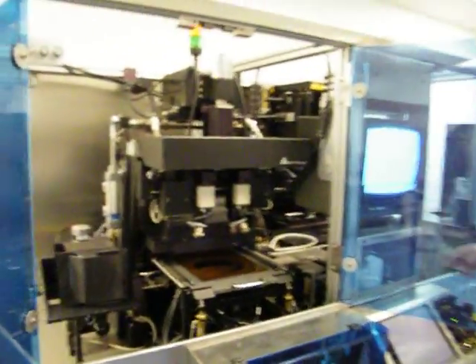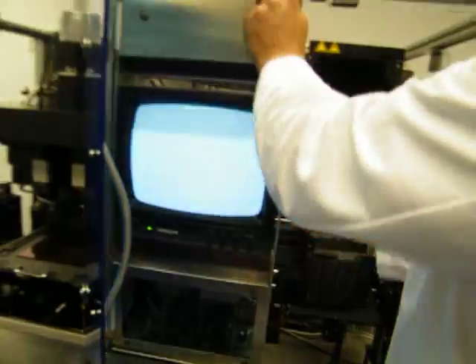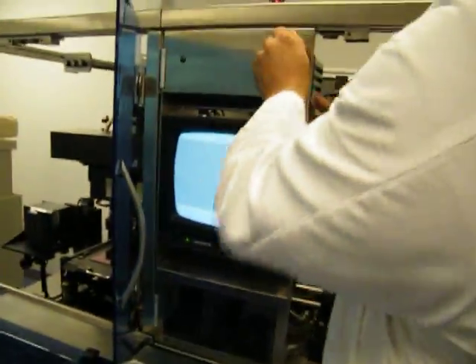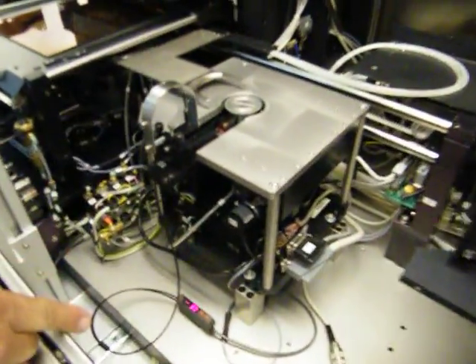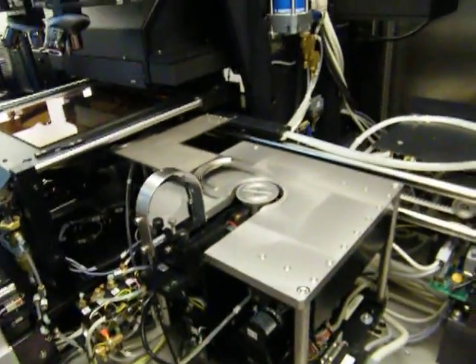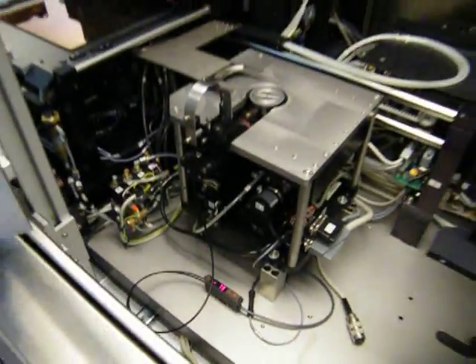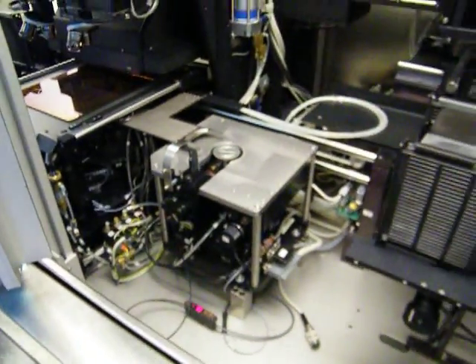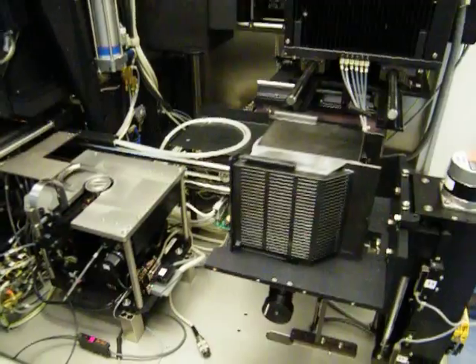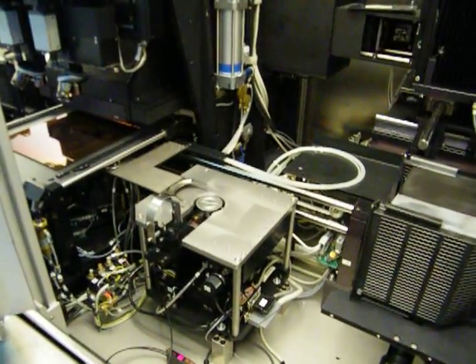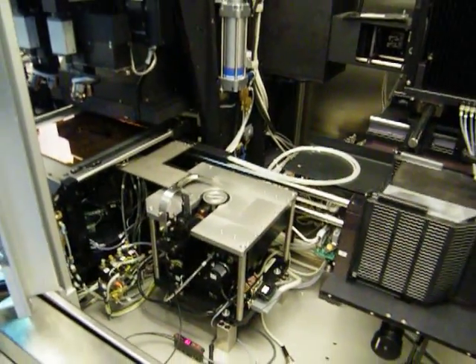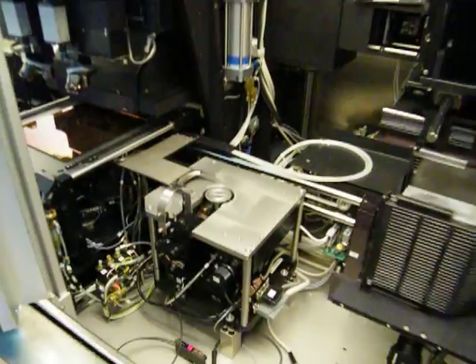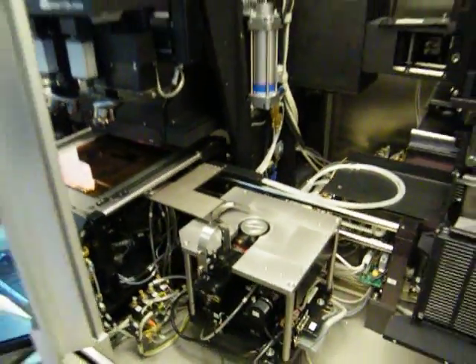And that's due to this Omron head here, which is actually a pretty big upgrade. This did not come from the factory like this. It's a pre-aligner sensor down here that runs through a fiber optic into this head. The prior owner also must have run some clear substrates or various different composition wafers, because a standard pre-aligner head would not work. It was a MEMS company that were running glass, so that does make sense.